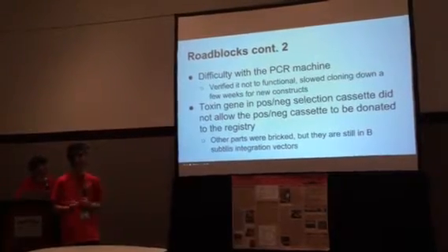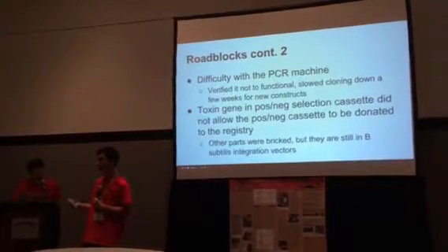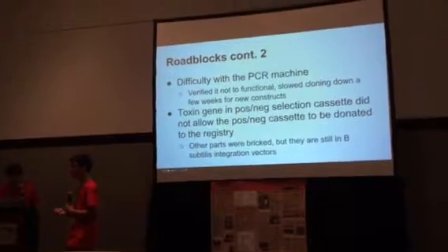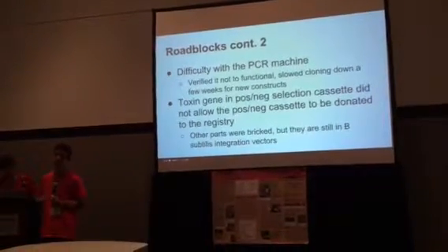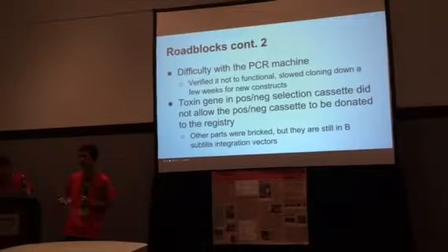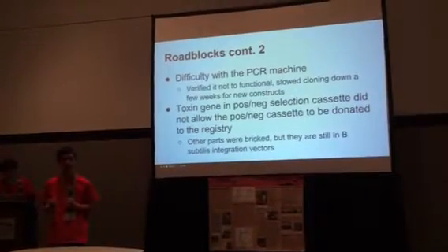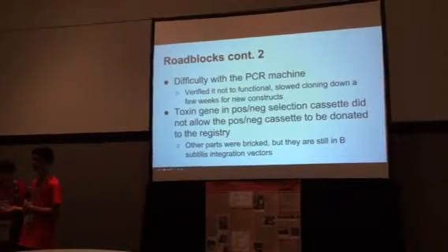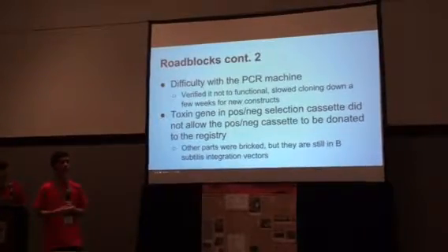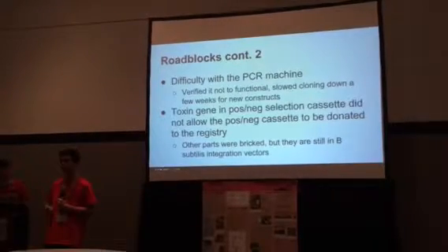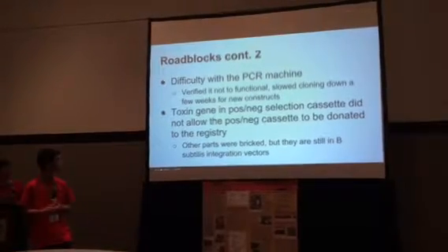And finally, there's also difficulty with the PCR machine. Since we're a hacker space and we don't have as many resources as many other hacker spaces or as many other labs, our PCR machine didn't heat up enough to actually denature the DNA for our PCR reaction. We used a thermometer to figure this out, and we also began using another PCR machine because all of our PCR machines are very old, 10 years.